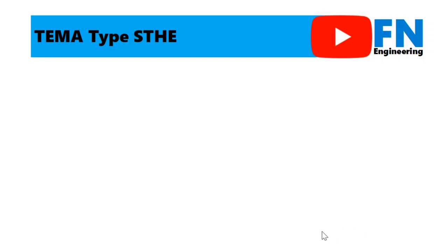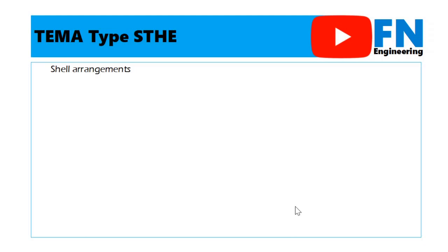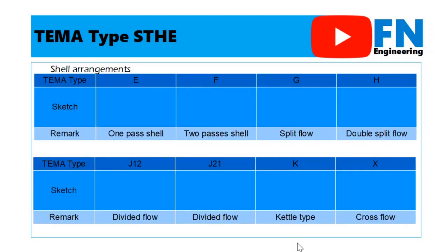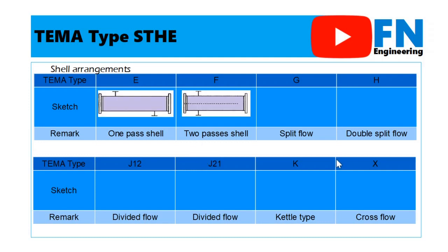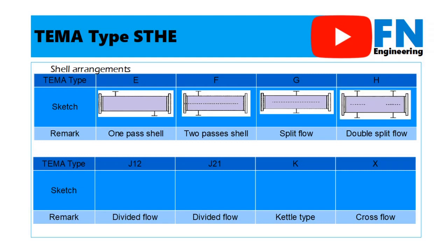The next configuration is shell arrangement. There are 8 configurations of the shell. Type E is 1 pass shell. Type F is 2 passes, so type F requires an impingement baffle. Type G and type H are for split flow. Single split flow is for type G and double split flow for type H.